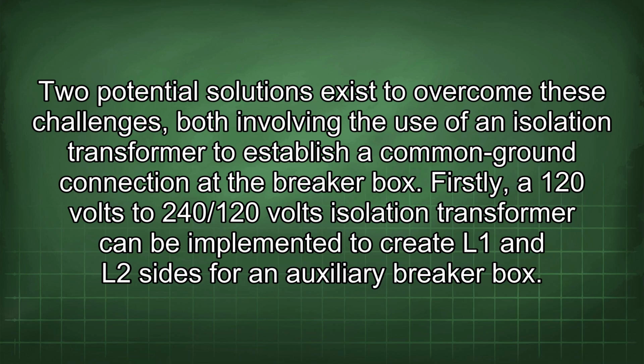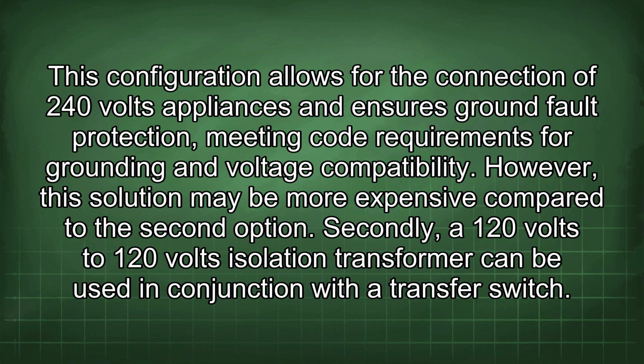Firstly, a 120 volts to 240/120 volts isolation transformer can be implemented to create L1 and L2 sides for an auxiliary breaker box. This configuration allows for the connection of 240 volts appliances and ensures ground fault protection, meeting code requirements for grounding and voltage compatibility. However, this solution may be more expensive compared to the second option.